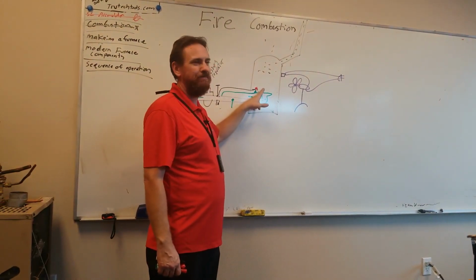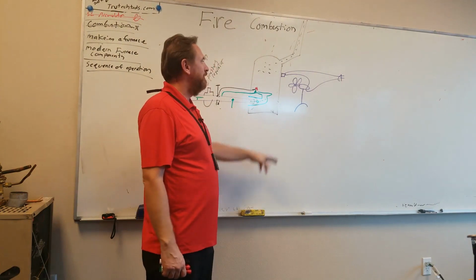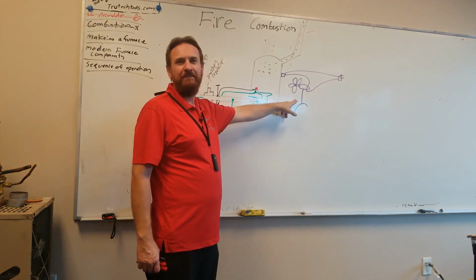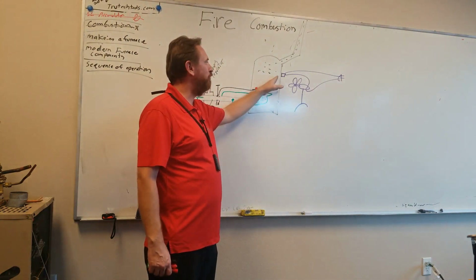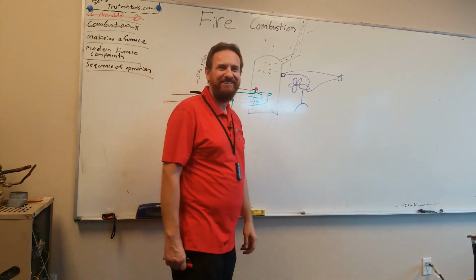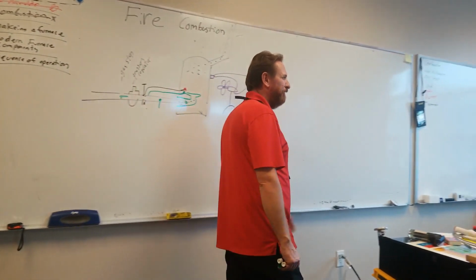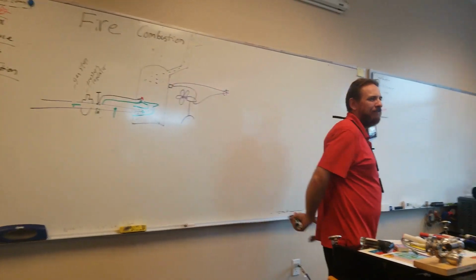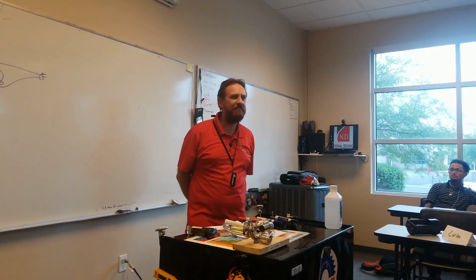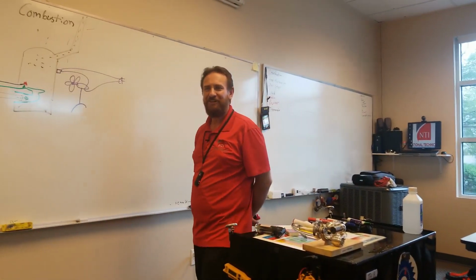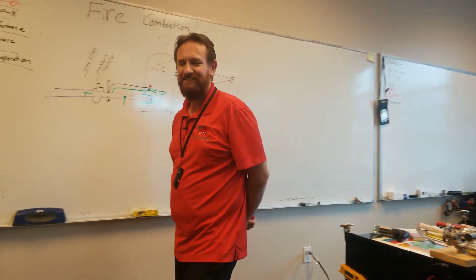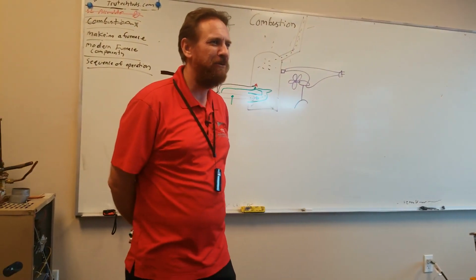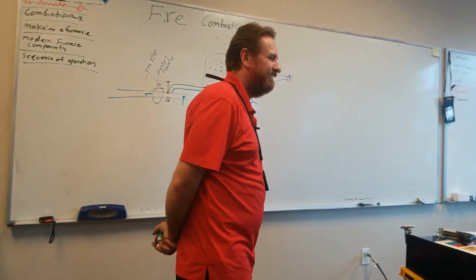What happens to my main flame? Goes out. Is this fan going to shut off immediately? No, it's going to stay on a little bit until it cools off this heat exchanger. Pretty neat, huh? You got a fully automated system. All you got to do is wake up every hour or so, run downstairs, and open and close that valve. Isn't that cool? Not that part. Oh, well, you want to automate it more? Is that what you're saying? Well, why not? Rather than wake up every hour.